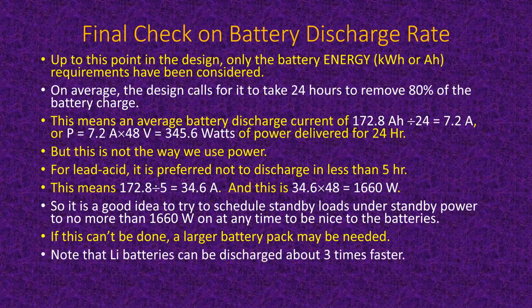Another nice thing about lithium batteries, you can discharge them almost 3 times faster than lead acid batteries with the same amount of loss. So the internal resistance of lithium batteries is a lot smaller than the internal resistance of lead acid. So you can charge them faster and you can discharge them faster without damaging the battery and without losing too much to heating up the batteries.